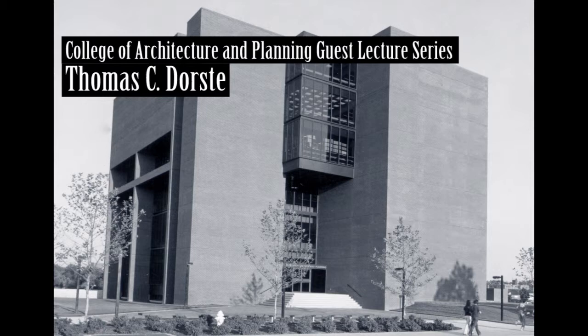This may be a little difficult. But the monitors on the roof are set in such a way, and the building is oriented in such a way, to pick up maximum sun source heat in the winter. The heat pump system and the return air are in the plenum so that this heat is picked up in the plenum, into the heat pump, back into the water system, used if there's heat needed, or stored if there's heat not needed. They have one building now designed this way, ready for bids, and once it's bid, we'll have solid information to determine what sort of capital investment that is and what sort of results we're going to get from it. It takes the normal advantage of a heat pump and uses that advantage to pick up solar heat of a passive nature.